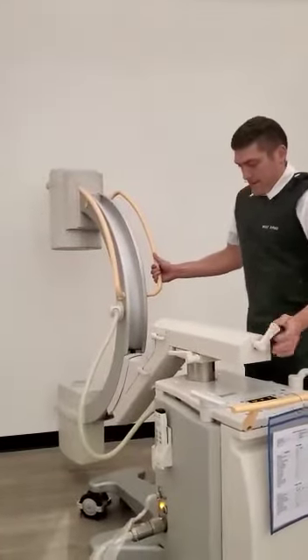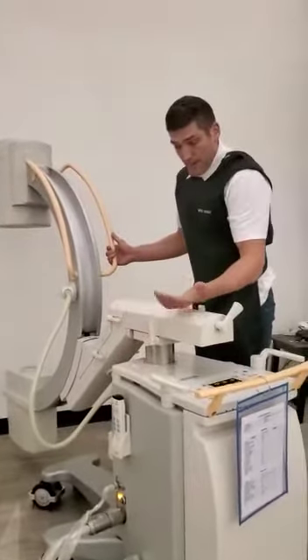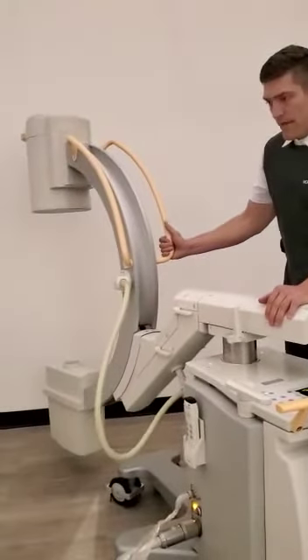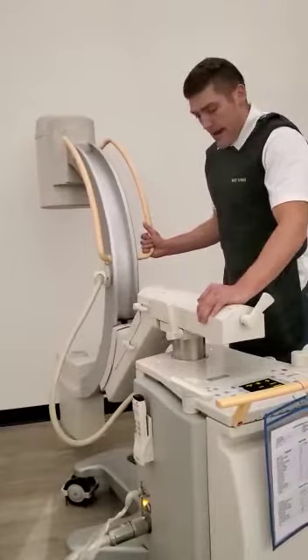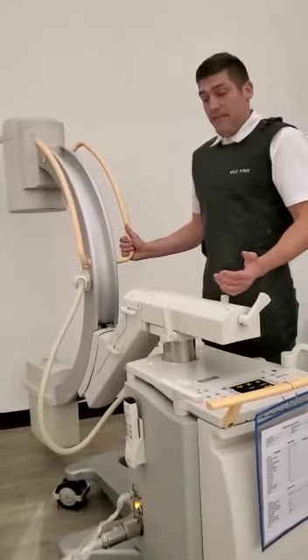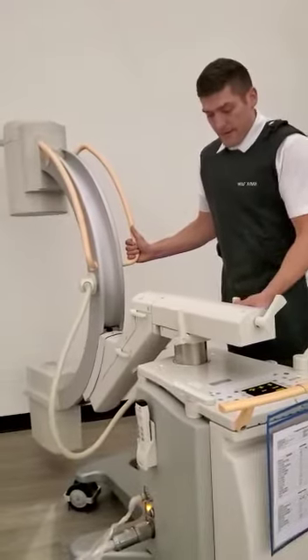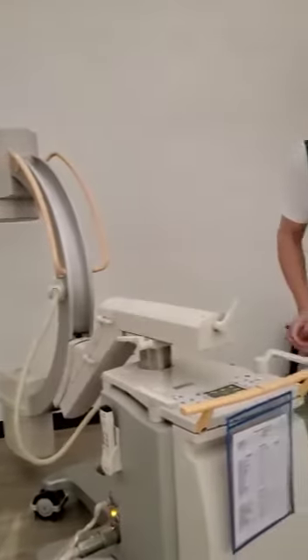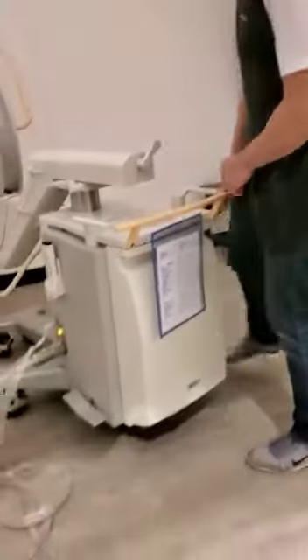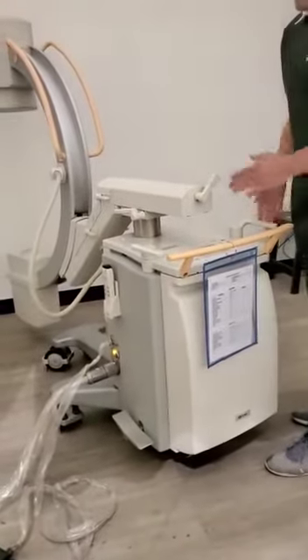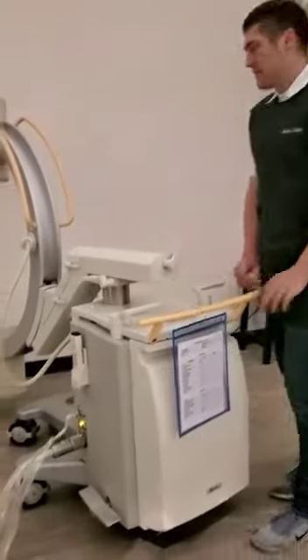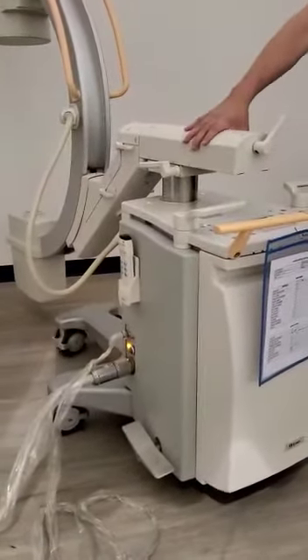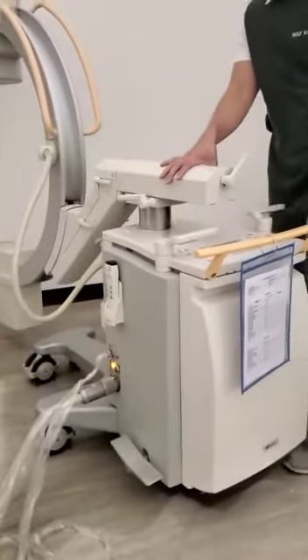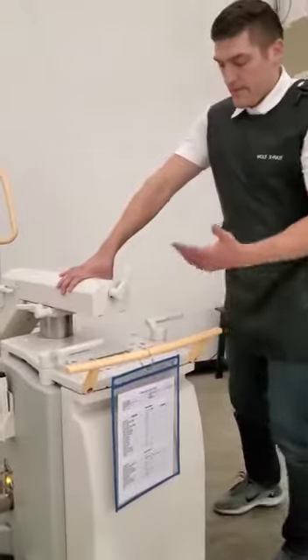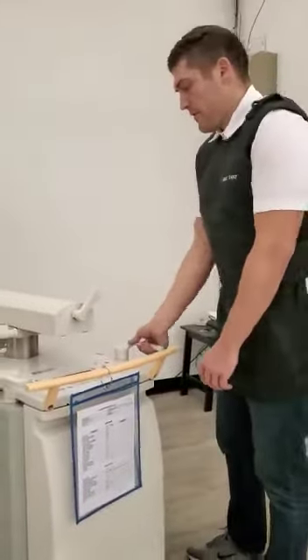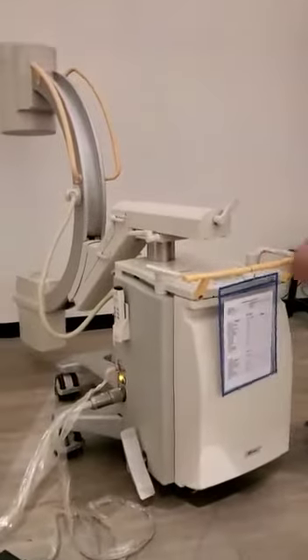Forward, back. This right here is your wig-wag or panning motion. To be exact, you have 12.5 inches either way. Now, if you need to go further than 1.5 feet, the easiest way to do this without moving the C-arm a ton is to unlock the system, use these levers, which move your wheels, put them in the lateral position, and now you can wig-wag and pan as far as you want if you need to go past 1.5 feet. It's just a trick or an easier way to move or to pan further than 12.5 inches.